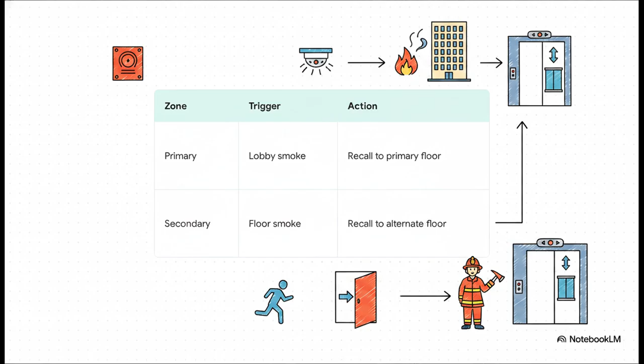But what if that primary floor has smoke too? Well, a secondary recall automatically sends it to an alternate safe floor. Programming this logic early guarantees safe occupant egress while instantly clearing the vertical path for firefighters.